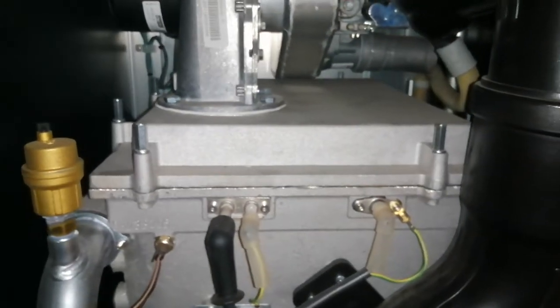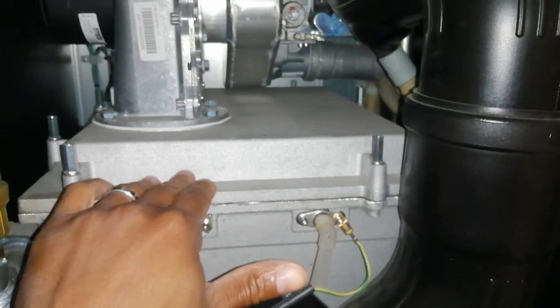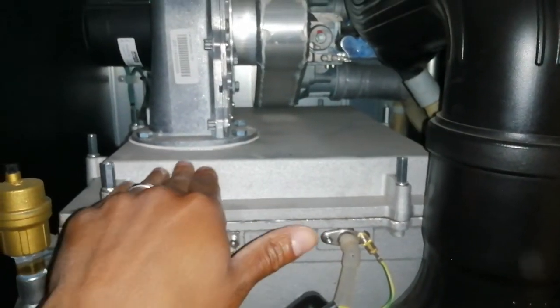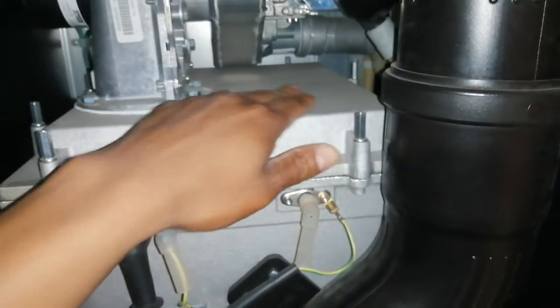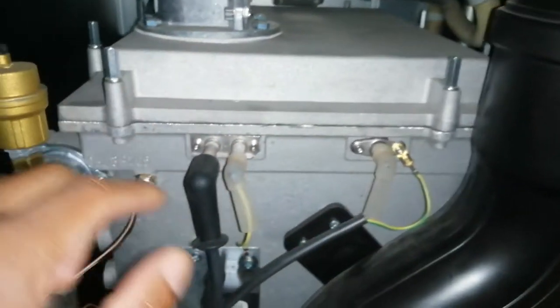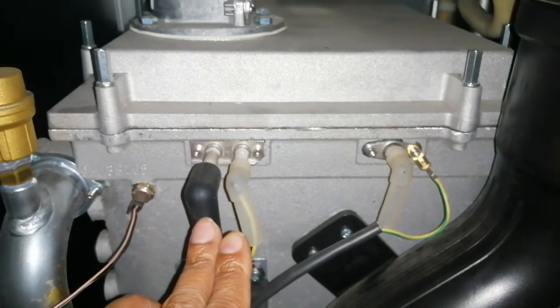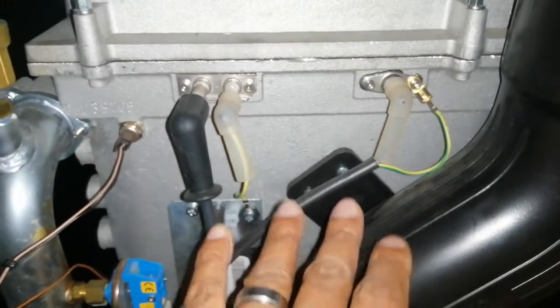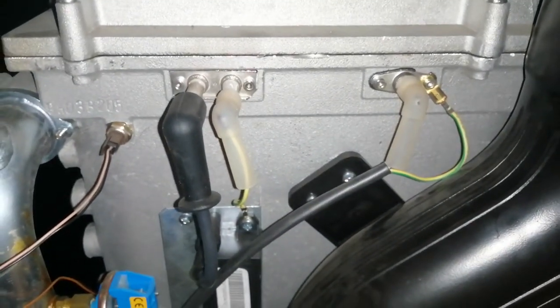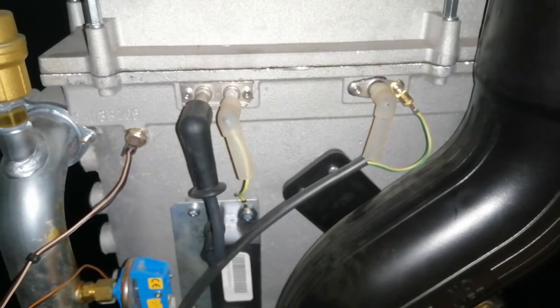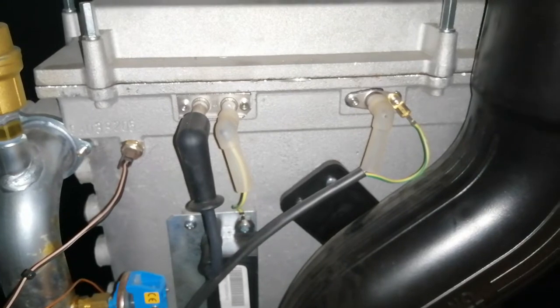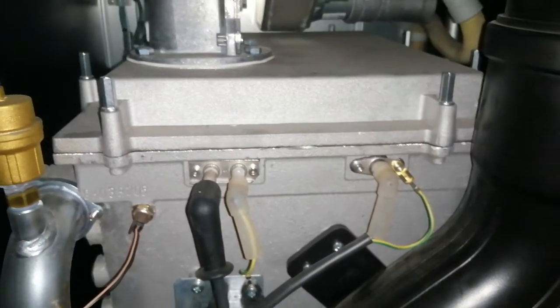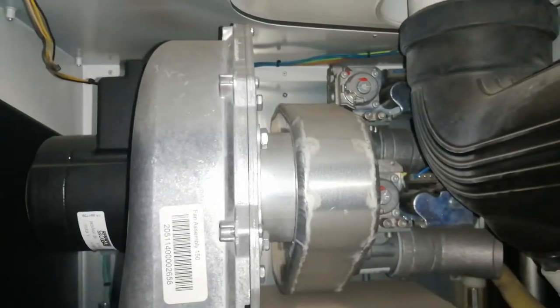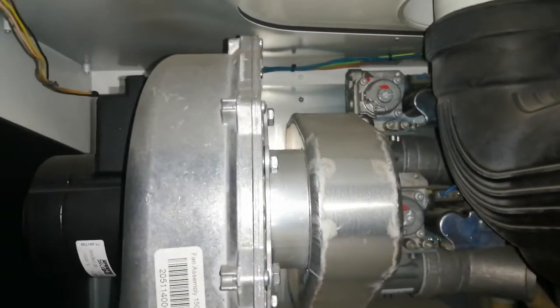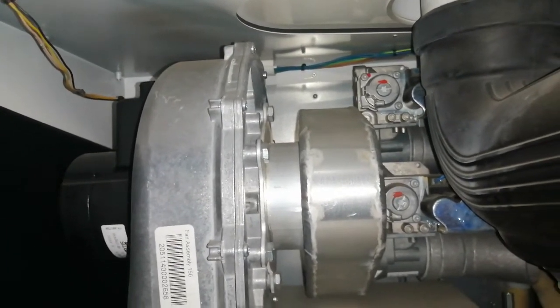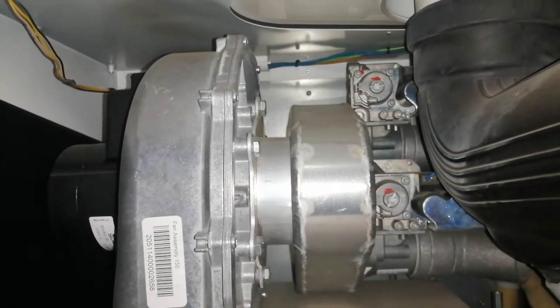On a major service you need to have a service kit so that you can break into the heat exchanger and give the burner a clean with a soft brush and flush about 4 to 5 litres through the heat exchanger. Ideally as well on a major service you want to be changing your probes, or if you can't change them then you can at least give them a clean with a file. Just file them down gently to clean up any debris off them. Also on a service, whilst you're carrying out your flue gas analysis, you want to be making adjustments to the gas valve so that it is in accordance with the manufacturer's instructions, so that your combustion readings are in line with what the manufacturer wants.